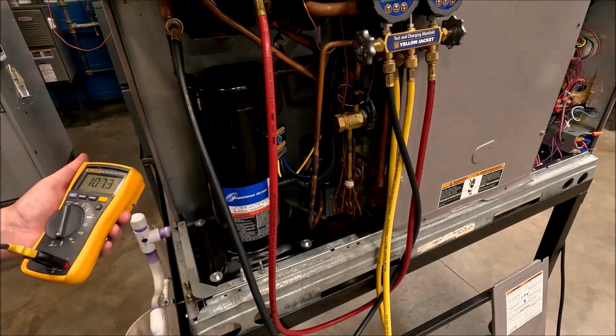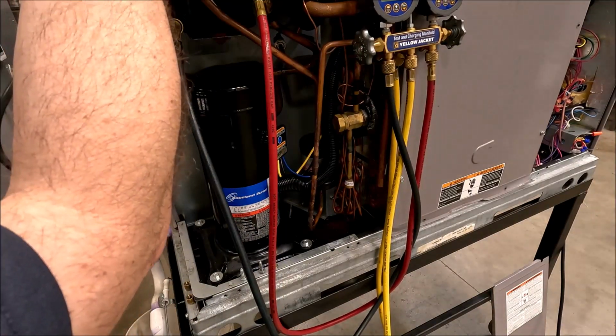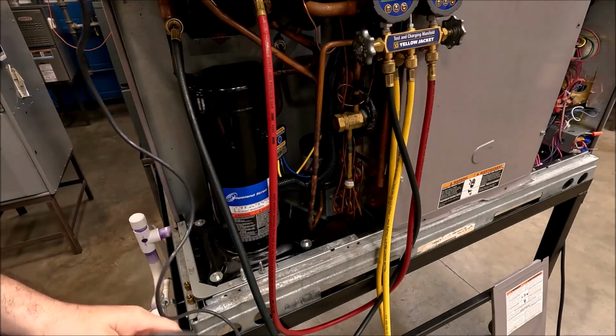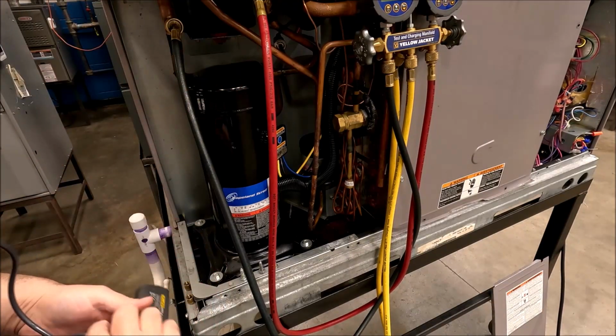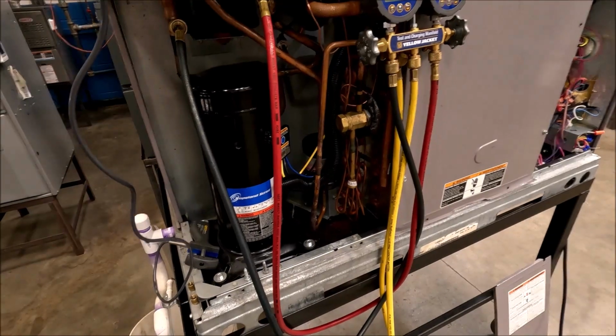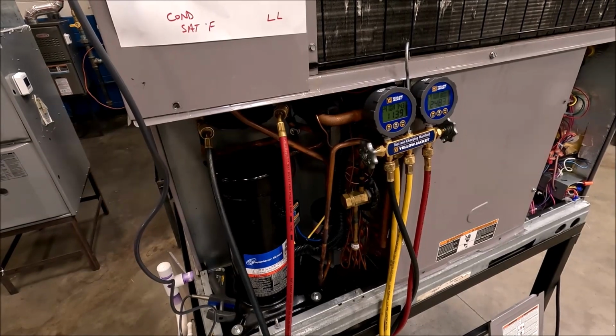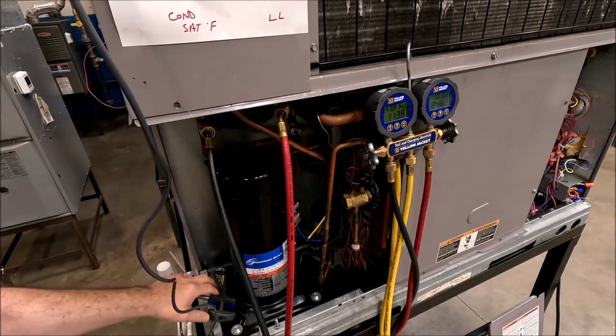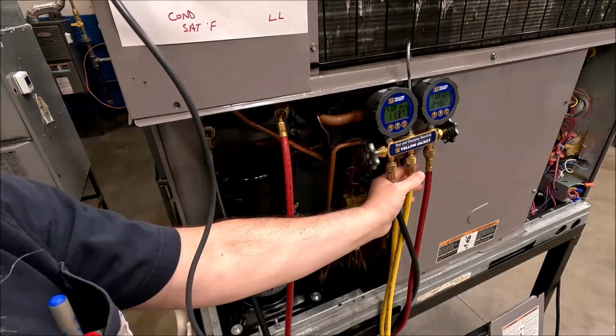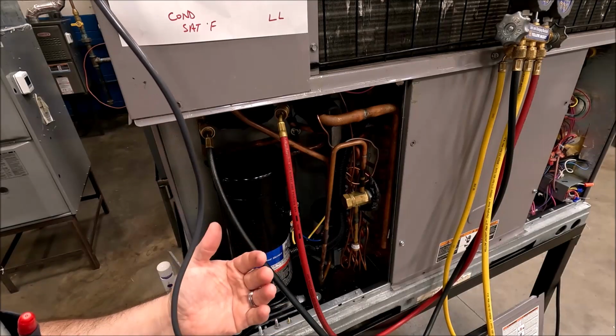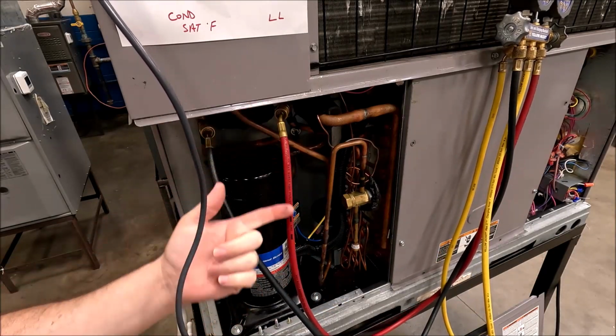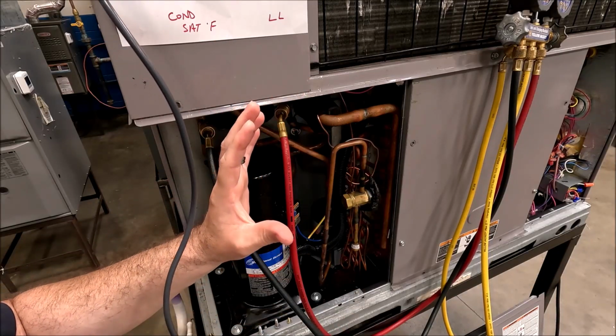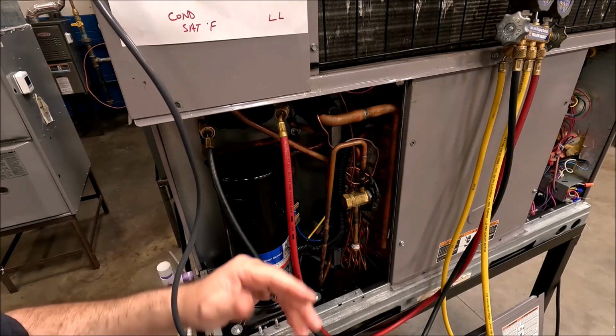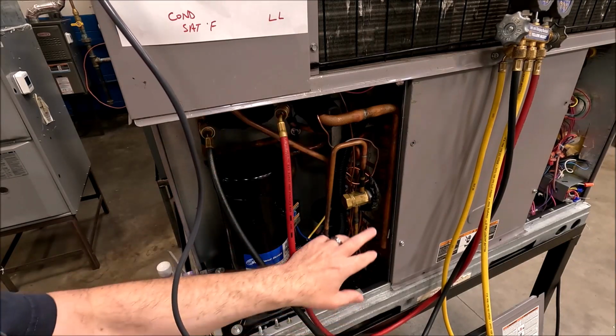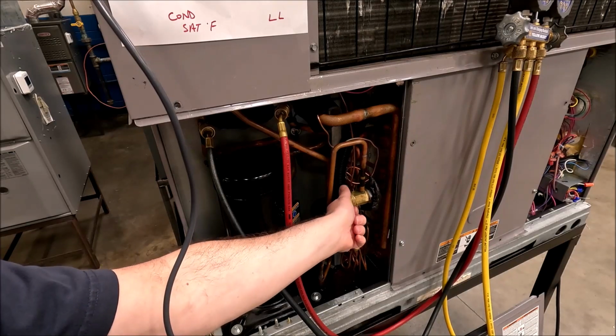Subcooling. Superheat is always at the end of the evaporator, and subcooling is always at the end of the condenser. So you have to know where the end of this condenser is. So the easiest thing for you to find in this package unit here, to identify the end of the condenser, is know the next component in the flow. My next component at the end of the condenser, as we look at it in like a paper example, a 2D representation, the condenser always flows to the metering device. And right here you'll see that you have a TXV on this system.